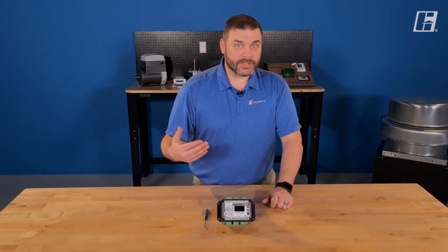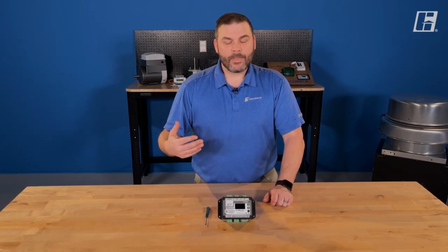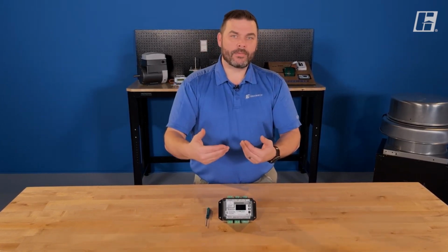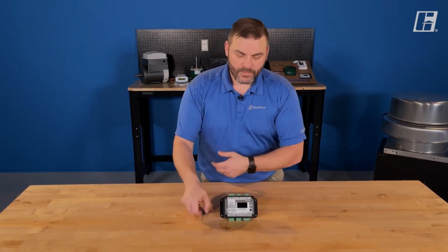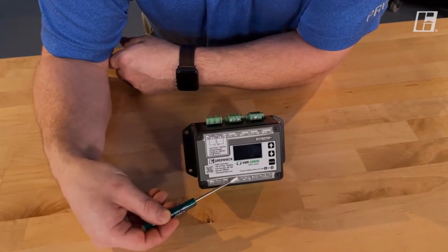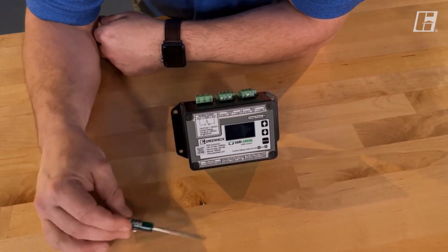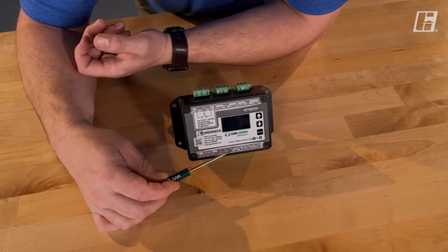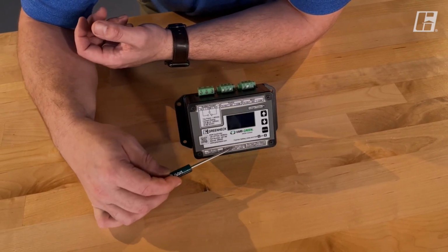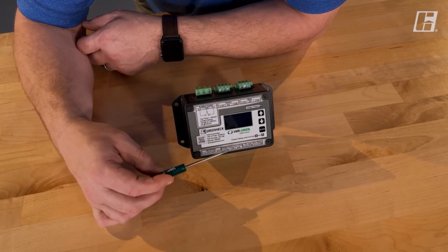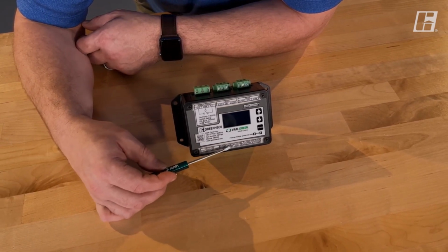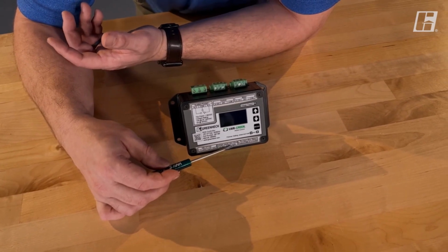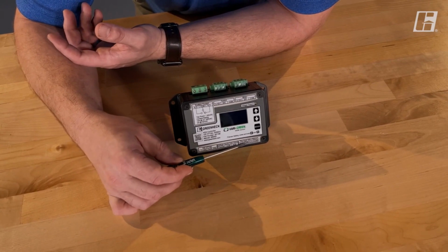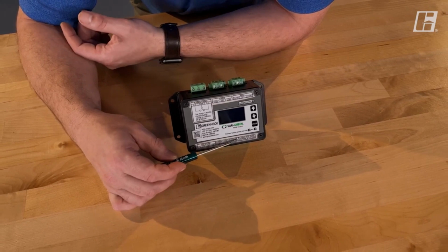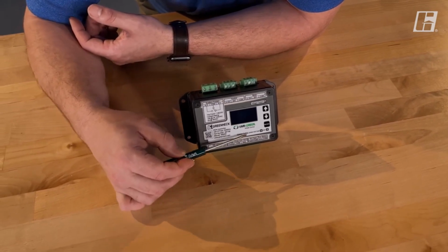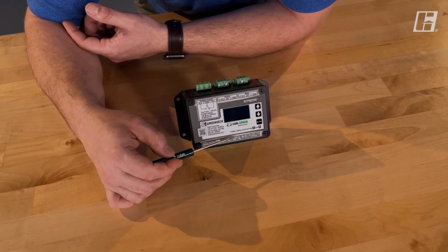The next set of terminals is that voltage input. That's that second common type of communication. Anytime I see voltage, you're telling me to run. Anytime you take that voltage away, you're telling me to stop. So let's look at those terminals. Here I can see my voltage input, I have my common, and I have my auto. Now I can use either of these terminals, or I can use both of them at the same time. Both of these are enacting that auto function of our handoff auto. This one, I'm simply seeing a difference in voltage, 0 volts on common, say 24 volts from your building management system on auto. Or over here, I'm seeing a contact closure on a time clock, etc. So I am able to use that remote auto input capability to turn this fan on and off.